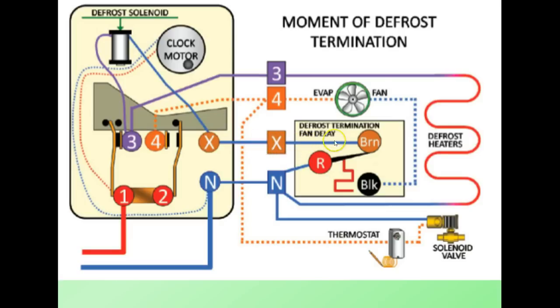The defrost solenoid now has a neutral control because we have closed this contact in the defrost termination fan delay, and we now have power to the defrost solenoid and it activates.